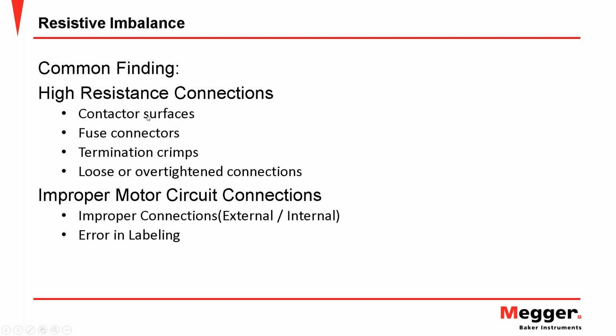They don't have good contact, if we're testing through those contactor surfaces. Of course, maybe ferrules in the fuse. Fuse connectors can become loose over time, or maybe some flaws in design, who knows. Those things can lead to high resistance connections. Loose or over tightened connections can also lead to high resistance. So those are the typical things that you find in the field.